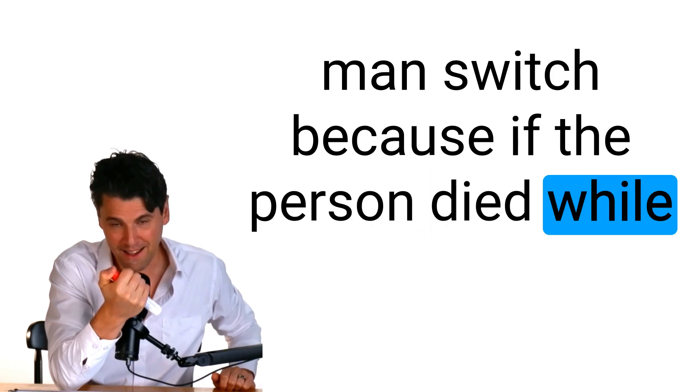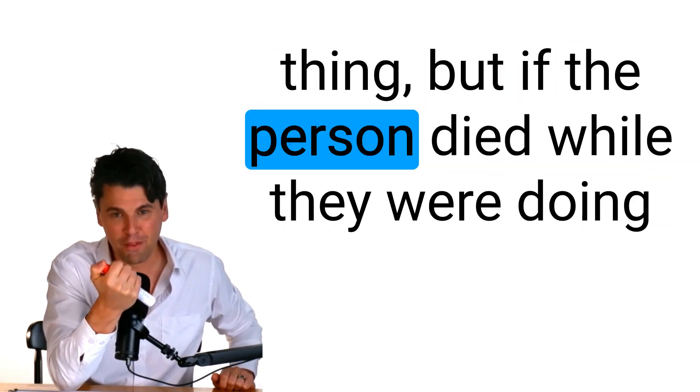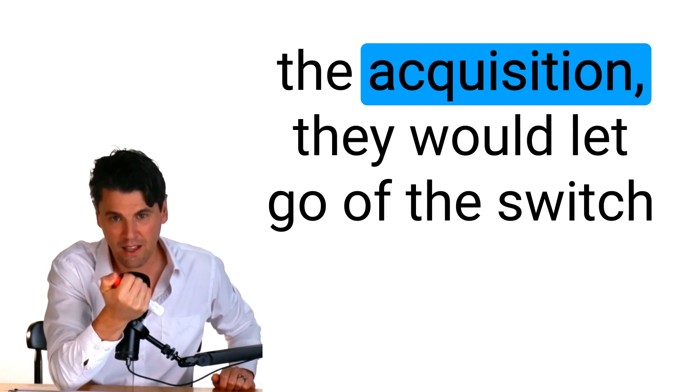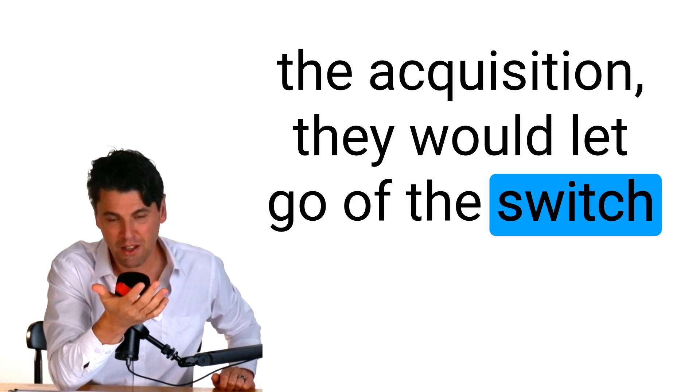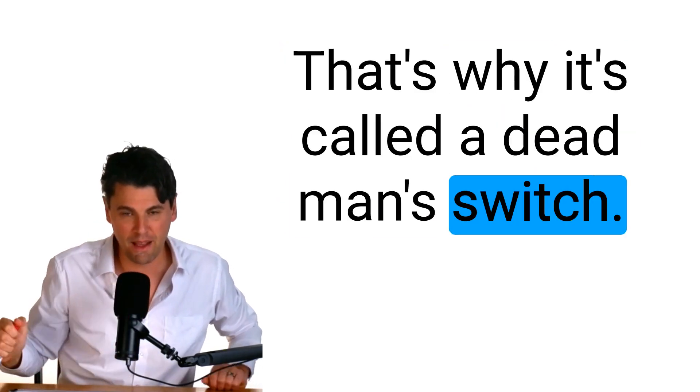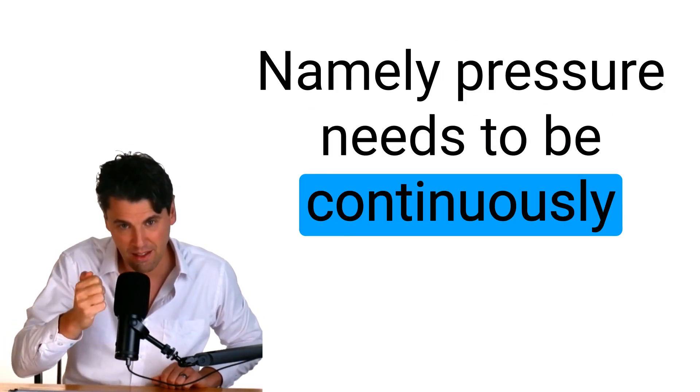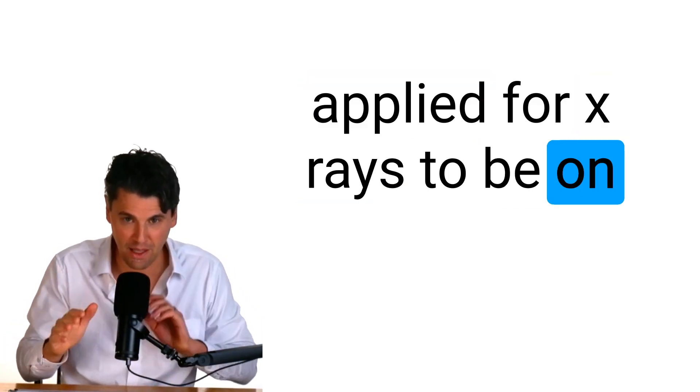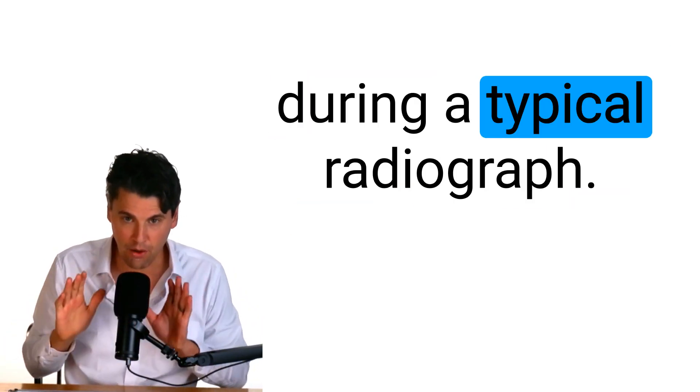You have to actually be physically applying pressure to a switch and it's called a dead man switch because if the person died while they were doing the acquisition, if the person died while they were doing the acquisition they would let go of the switch and the x-ray would turn off. That's why it's called a dead man switch, namely pressure needs to be continuously applied for x-rays to be on during a typical radiograph.